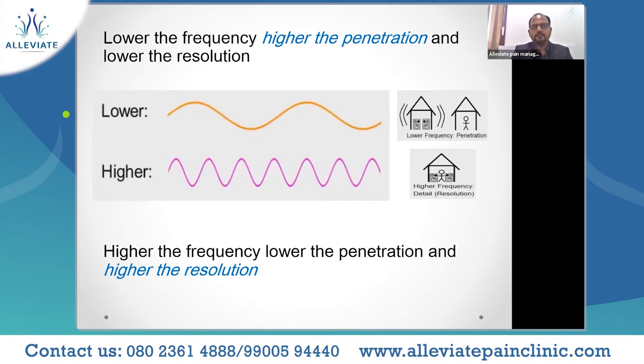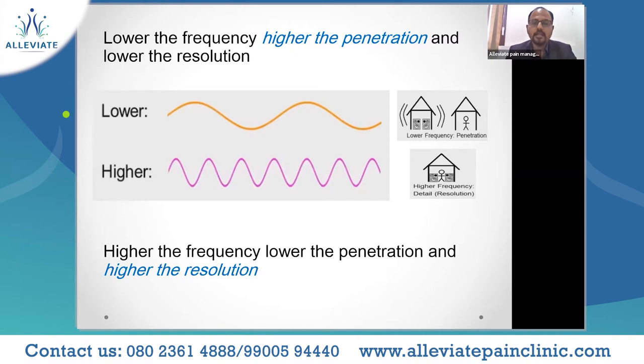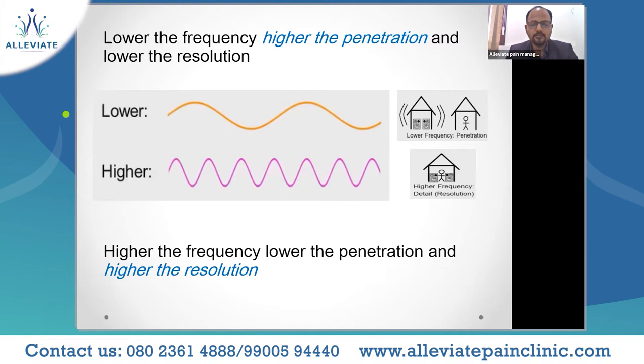As a clinician trying to achieve precision, resolution is important — it is very important to see the structures where we intend to do procedures or needling, such as the tip of the needle. That is achieved at higher frequency: at higher frequency, resolution is very detailed, but penetration is poor. This helps us choose based on the depth of our intended target. If the target is beyond 4 centimeters, it is advised to use lower frequency probes; for superficial structures, we use higher frequency probes where resolution is better.